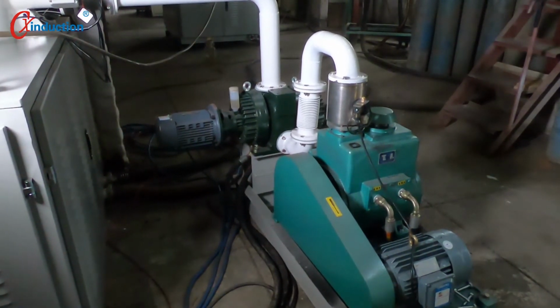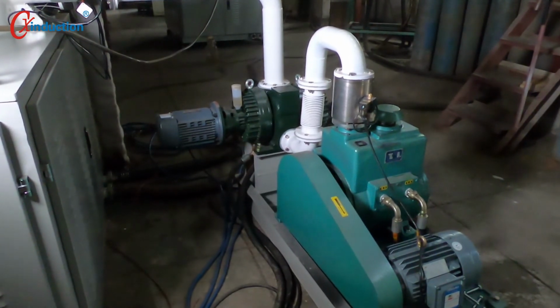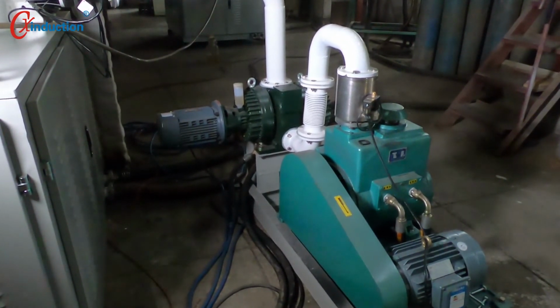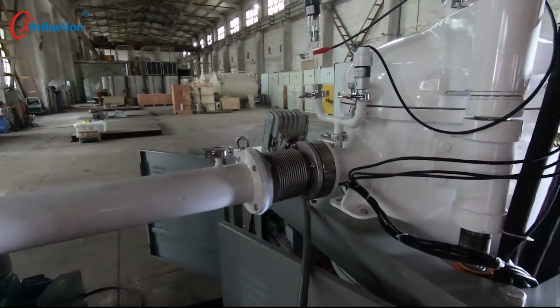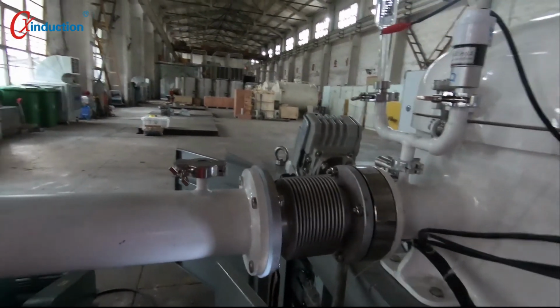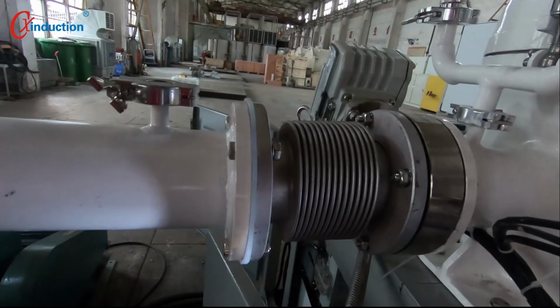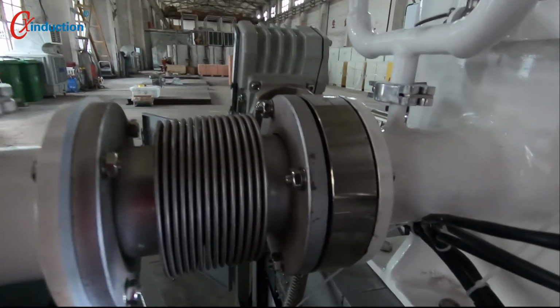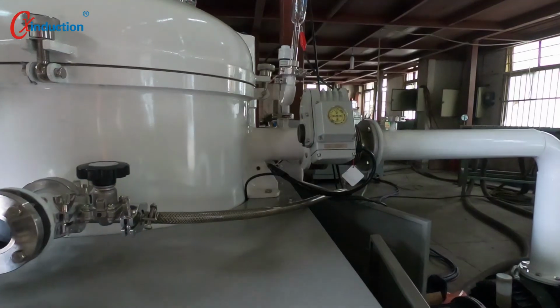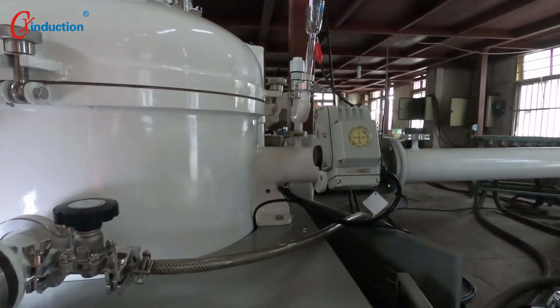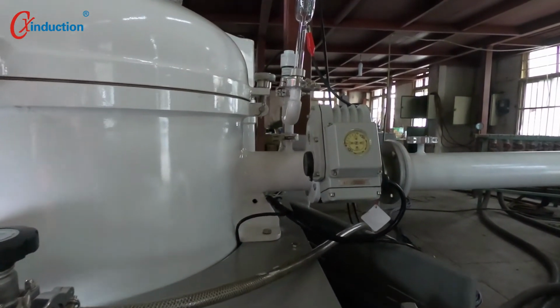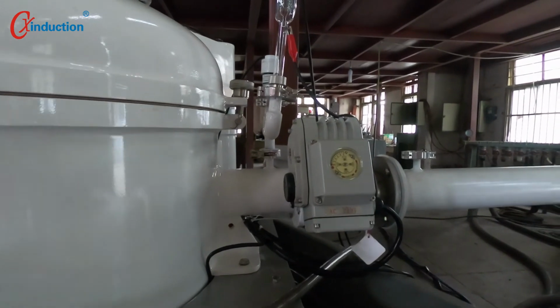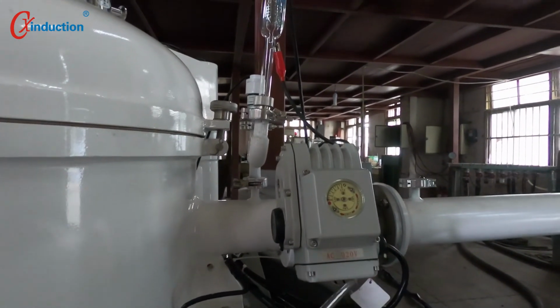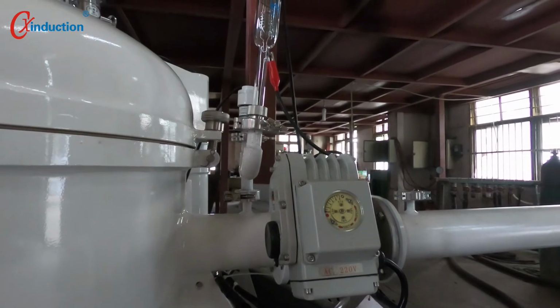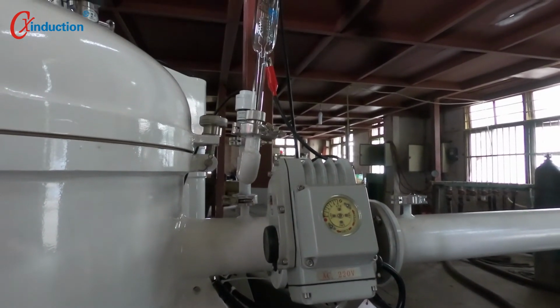4. Vacuum system. There are a rotary vane pump and a roots pump which evacuate the furnace body from the furnace side. There's an anti-vibrating bellow installed on the channel between the vacuum pump and the furnace body, which effectively prevents the furnace vibration generated by the vacuum pump during operation. It is equipped with an electronic vacuum valve on the channel. There is also an electromagnetic vacuum charging valve before the rotary pump, which works with the vacuum pump to avoid returning oil to the vacuum pipe after stopping the pump.